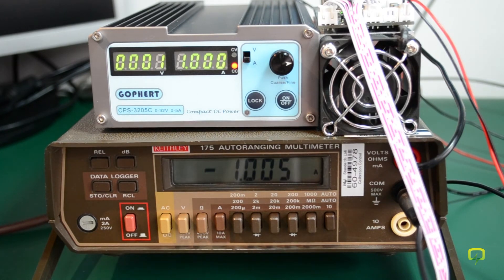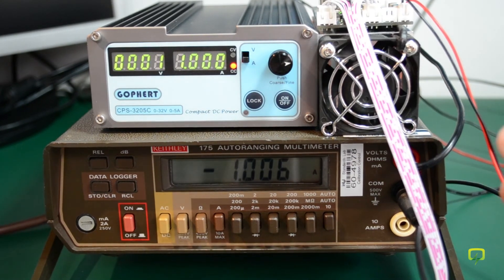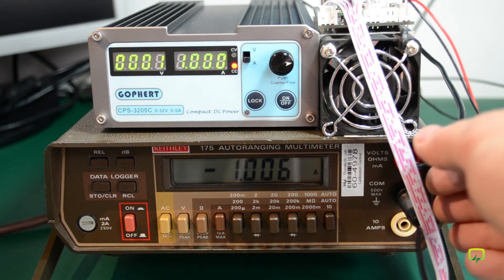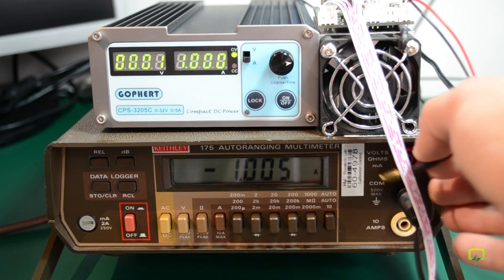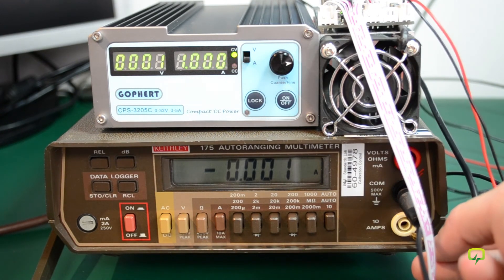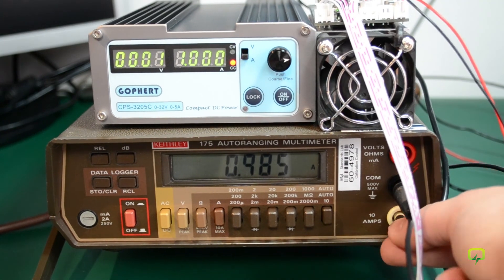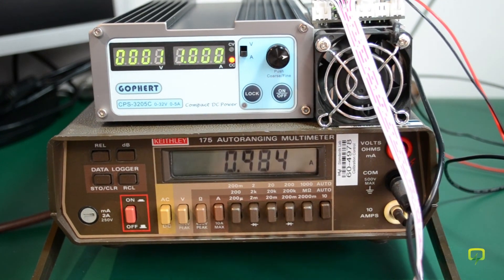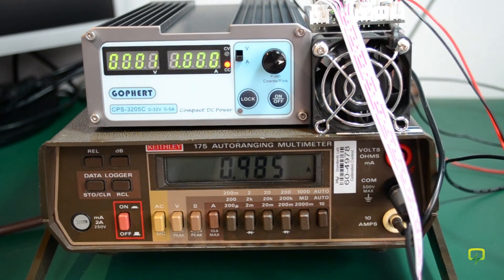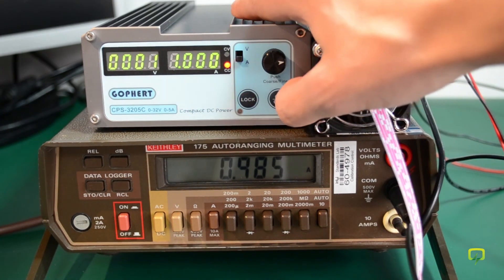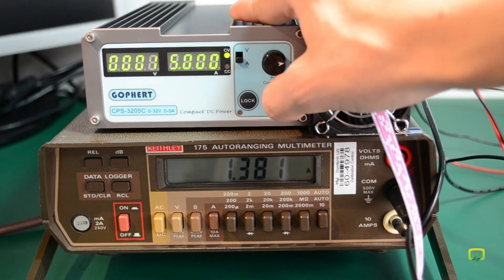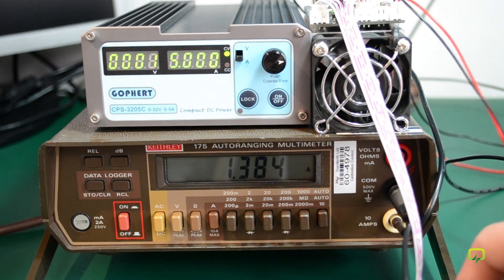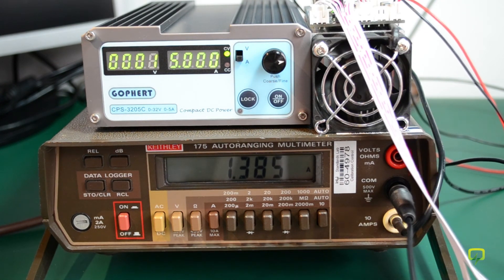Next, I'm going to move the multimeter on the 10 amp range because the next calibration mark is at 5 amps. Alright. And now if I press the on/off button, the power supply should jump to the 5 amp calibration. I need to adjust my dummy load.